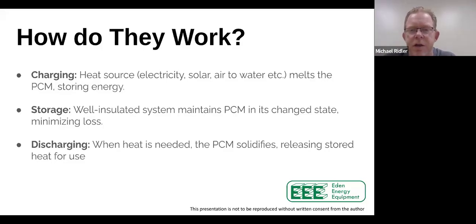But the key thing is the very high energy density and the very low standby losses. A phase change battery's standby loss is going to be anywhere from 0.4 to 0.8 kilowatt hours, whereas a traditional water heater is going to be a factor of like 1.5 to 2.5 kilowatt hours. That's because the phase change battery is very compact by its engineering, which makes for a really well insulated system.